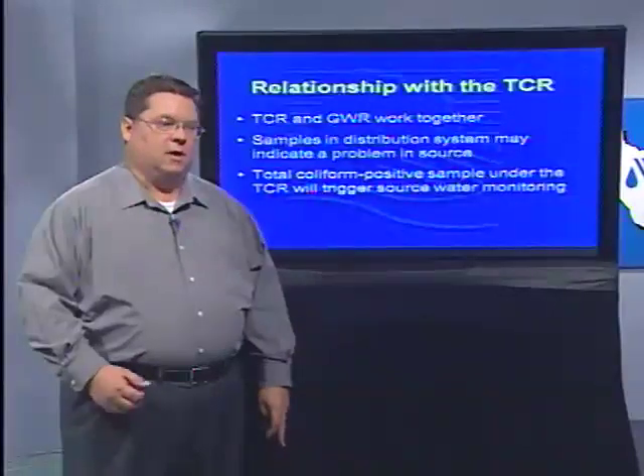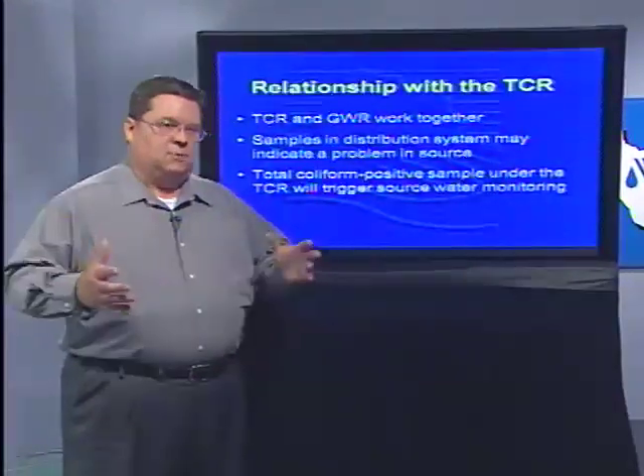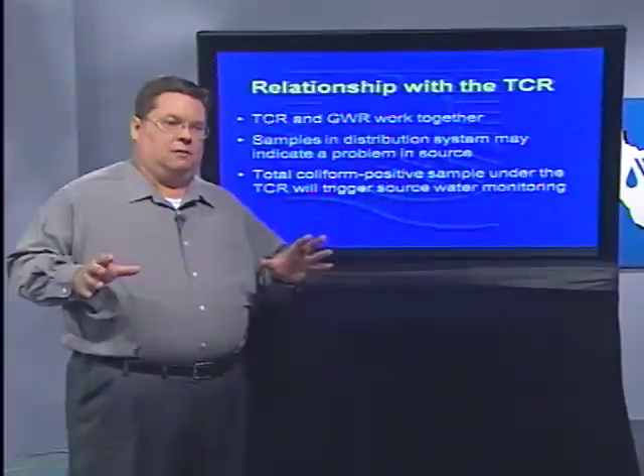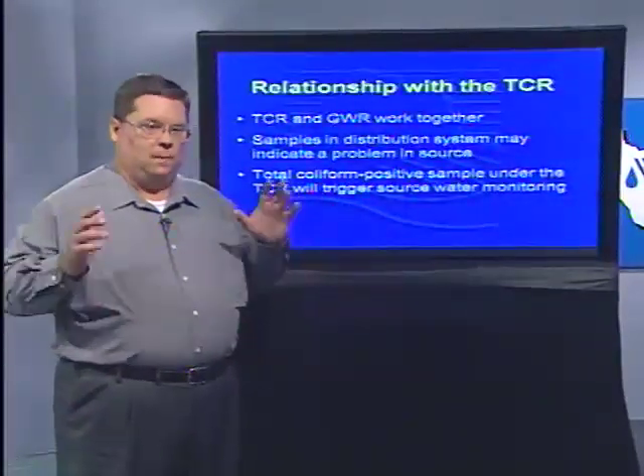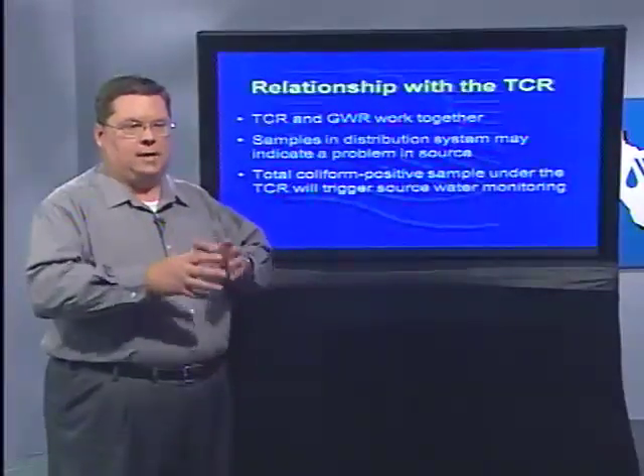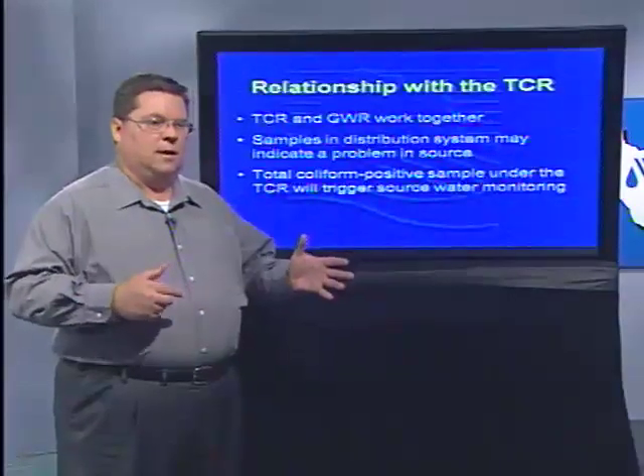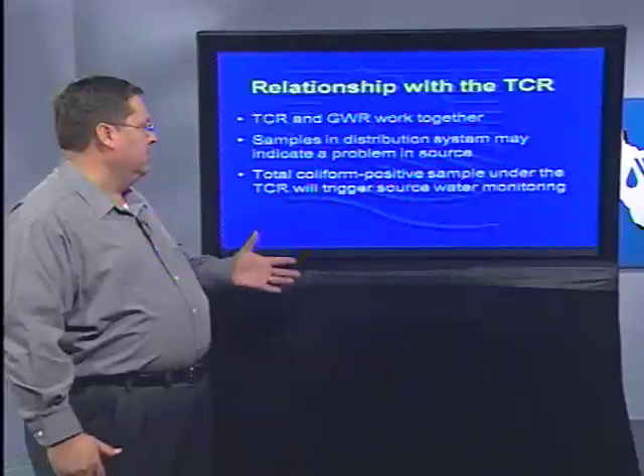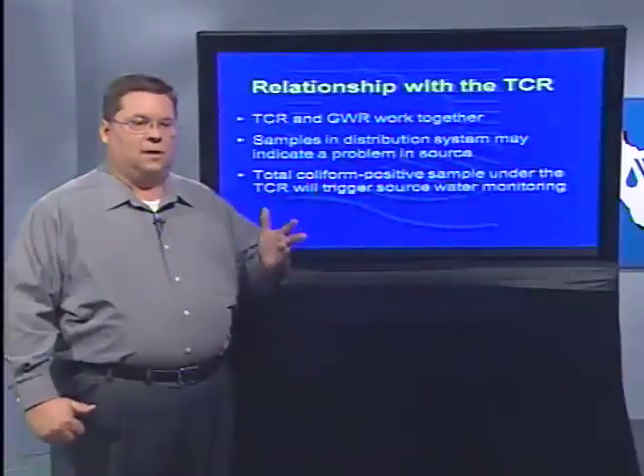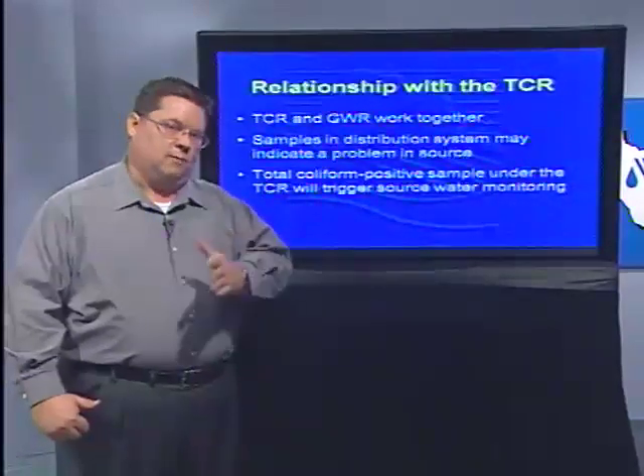Another common question regarding the Groundwater Rule is: does this mean that the Total Coliform Rule goes out the door? The answer is that the TCR stays in place. They work in conjunction with each other. You start out with the Total Coliform Rule and they work together. Samples in a distribution system may indicate a problem in your source. Total coliform positive samples under the Total Coliform Rule will trigger source water monitoring.